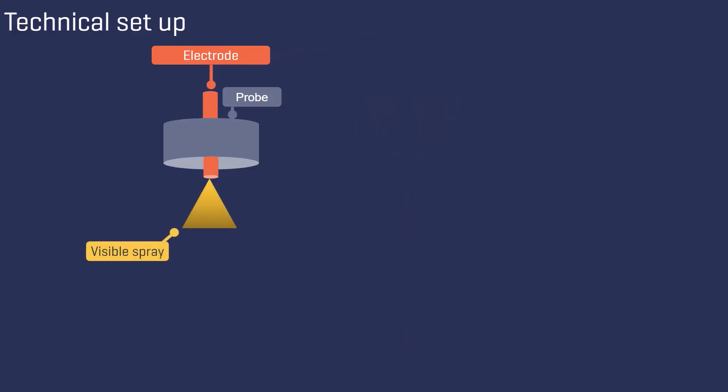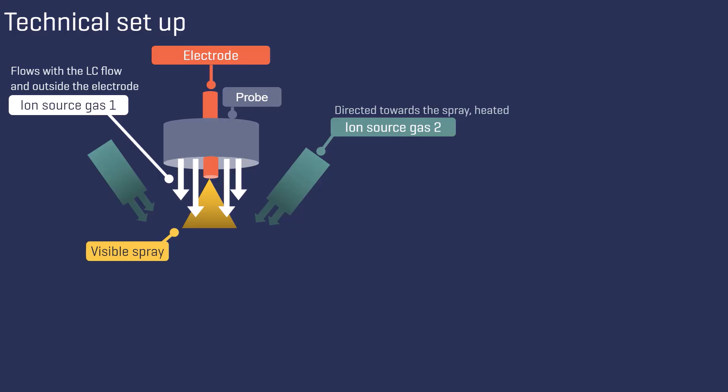The process is supported by different gas flows. Ion source gas 1 flows in the same direction as the LC flow, between the inner wall of the probe and the outer surface of the electrode. Ion source gas 2 is directed towards the spray and heated by the heaters.